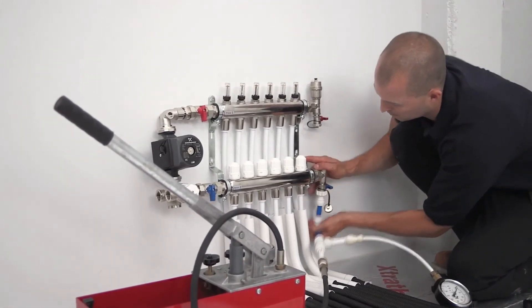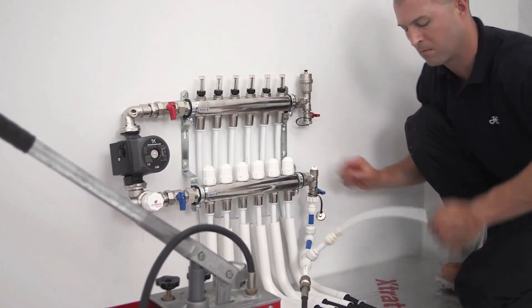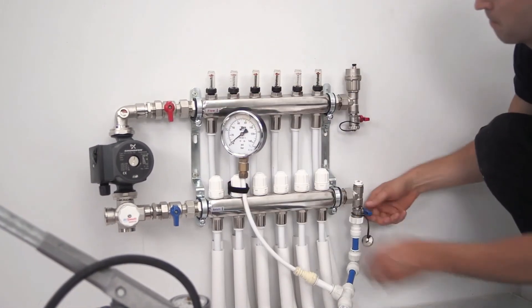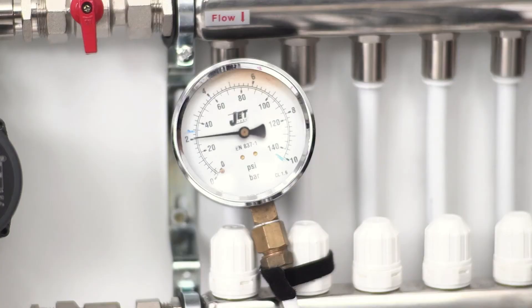Connect a suitable pressure testing kit to one of the fill valves. With the valve open, pump up the pressure to two bar. Isolate the pressure at the tester and leave for 10 minutes while checking for leaks or pressure drops.